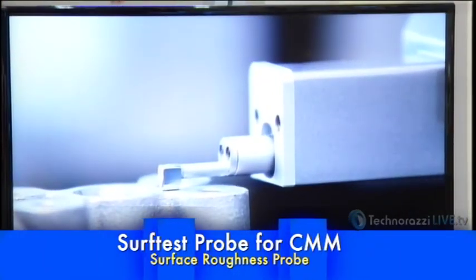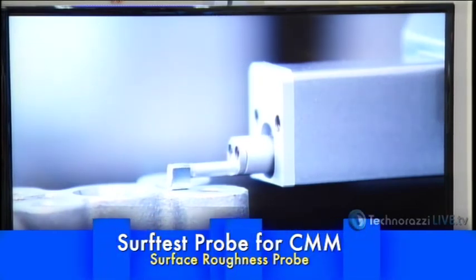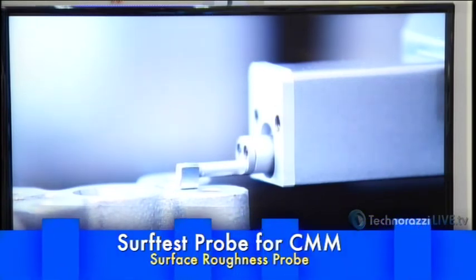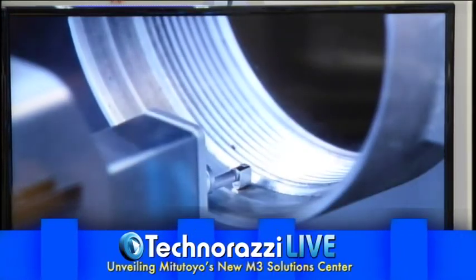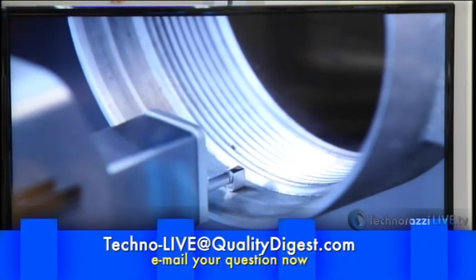Sure. There we go. As you see, the probe is over the part right now, and it's making the trace. It's a skidded detector, so the diamond is actually making contact with the part. As it's doing that, it's taking measurements, and it's processing the data through our software. And because it's on a CMM, you can put this anywhere you want, just like you would a CMM probe. Correct. So in this case, you've gone inside some sort of part here. Correct. And there's various probes and styluses that you can use with it. There's different styluses for different applications.